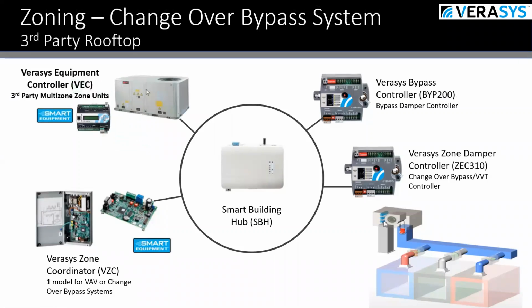Now, for a third-party rooftop, it's a little bit different. If you have a Trane or a Carrier or Lennox with a changeover bypass system, it can still handle up to 32 zones on that bus. But with these, you can't talk directly from the zone coordinator to the unit. You have to have a controller to make that tie-in to connect the two.